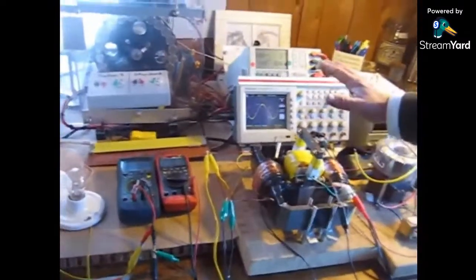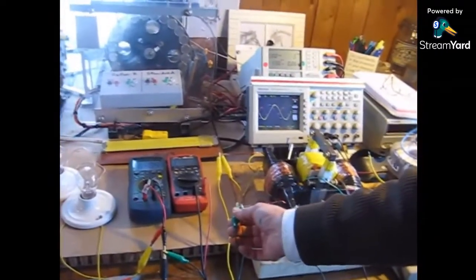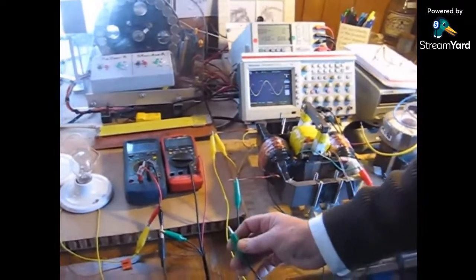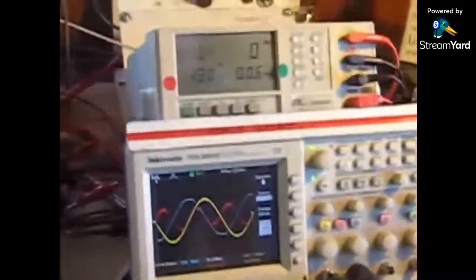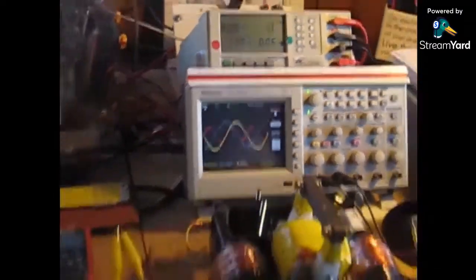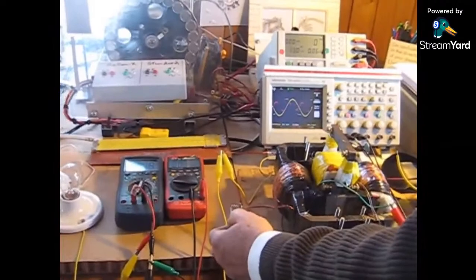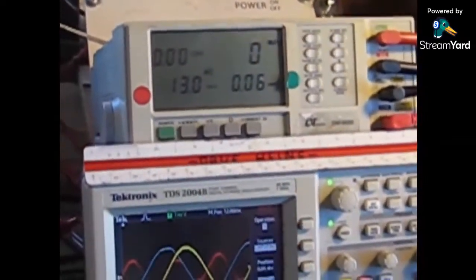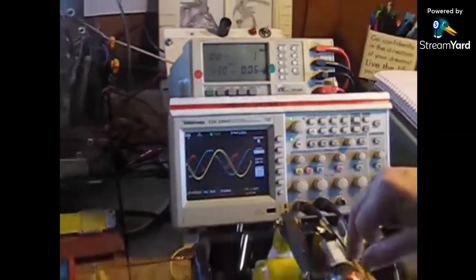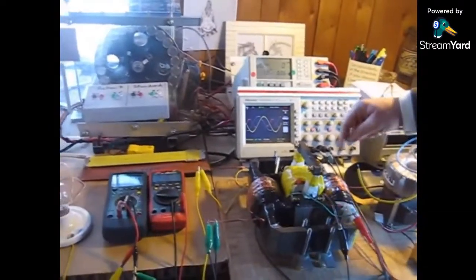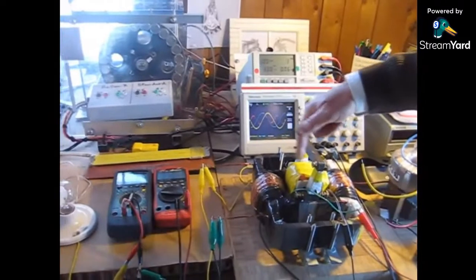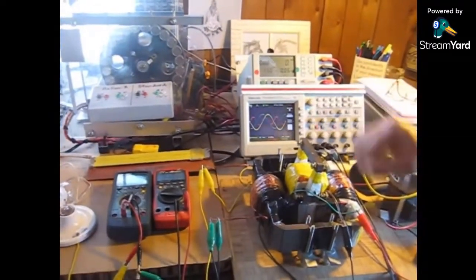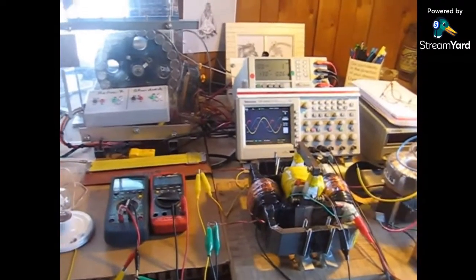And so when we put the bitoroid transformer on load from no load, there's absolutely no change in the input to the primary of the bitoroid transformer, because there's no secondary flux coupling back through the primary affecting the performance of the primary from no load to on load.